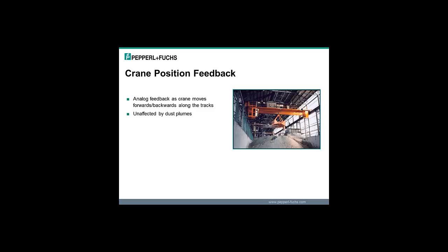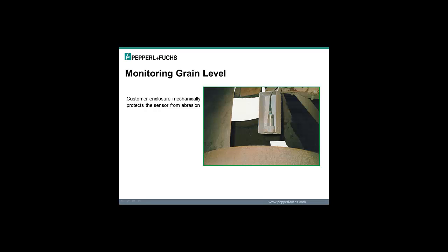Looking at the level of grains, again, another level application, but you can see here the customer, as things get dumped from the top, they didn't want the sensor to get beaten up, so they put this protective cover on it, and that allowed the sensor to look through the opening in the bottom to detect the level, but not get pelted by the things that are dropping from above.